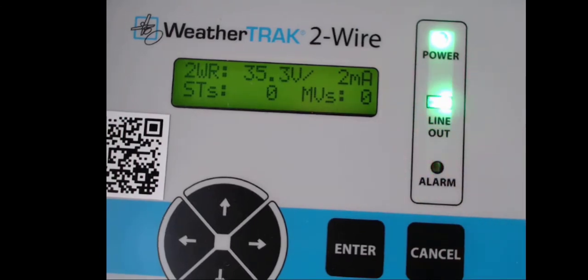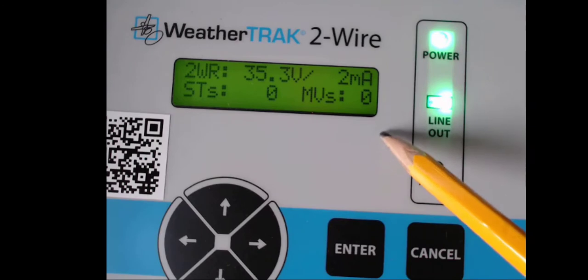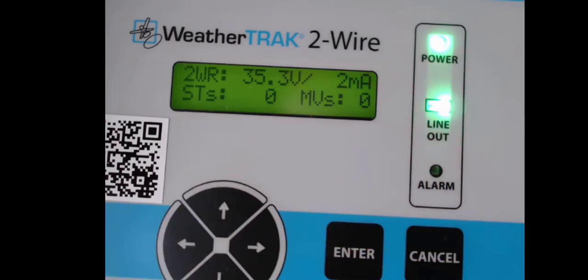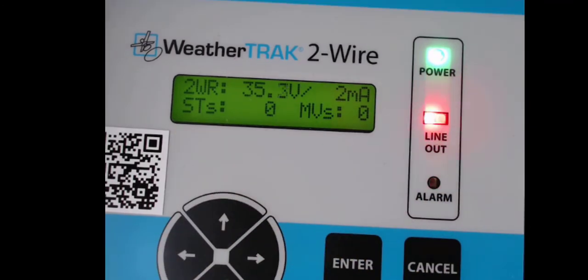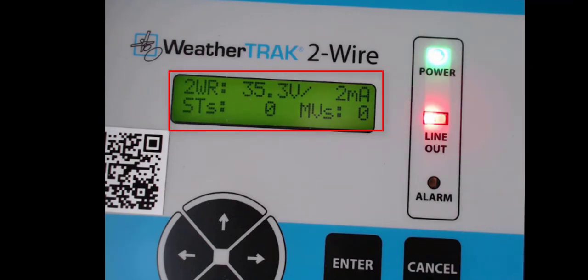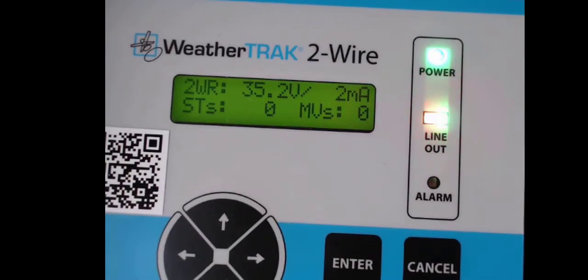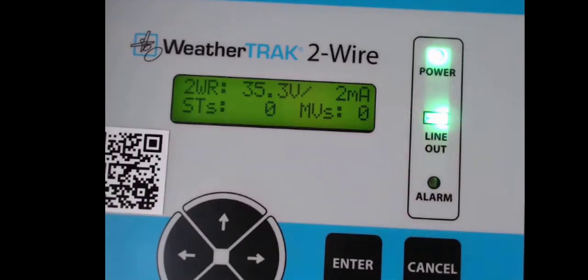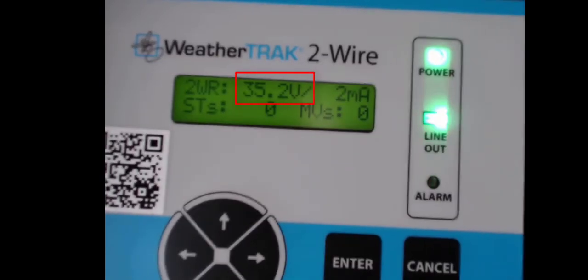Once you have identified that it is an issue with the 2-Wire path, you will want to focus on the 2-Wire interface. On the 2-Wire interface we see first our LED diagnostics and our digital screen along with the buttons that help us manage the menus. If the problem is on the 2-Wire path, there will usually be an alert present on this display. The display will highlight the vital information we need to manage the 2-Wire path and controller. The first item we see is the voltage being delivered down that path.